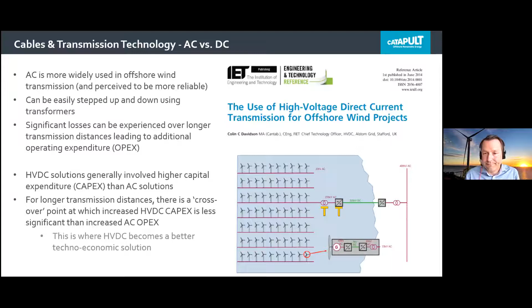That crossover point isn't fixed. You can't say that if your offshore wind farm is greater than 100 kilometers offshore it's always going to be HVDC, because the factors driving that techno-economic study will change and the crossover point will move. But it's kind of in that range - 80 to 100 kilometers, sometimes a little less. And then you may have a technology breakthrough in one area and it moves. But that's kind of the story.